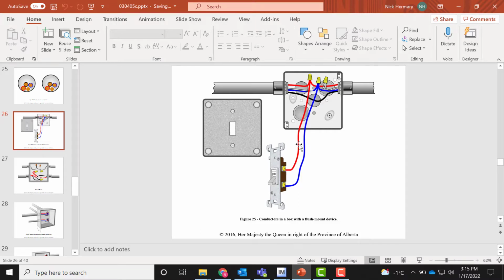Then it goes to subrule 2, and it says the wire connectors. Okay, so we're going to deal with these now, these wire connectors, wire nuts, Marrettes, whatever you want to call them. Basically it says that we're going to count some wires for other things taking up space, including these wire connectors. So 2B says, one insulated conductor for every pair of conductor connectors with insulating caps.